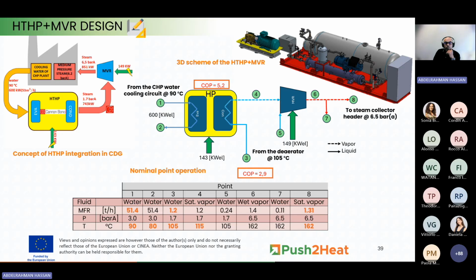Then we will use the mechanical vapor compression system to increase the pressure at point 6 to 6.5 bar A. Here we will inject water in this compressor to cool it down and also ensure that the outlet at point 6 is wet or saturated vapor. Then at point 7, we will extract any water droplets from the outlet, and point 8 is saturated steam, which is integrated into the steam collector header at 6.5 bar(a).